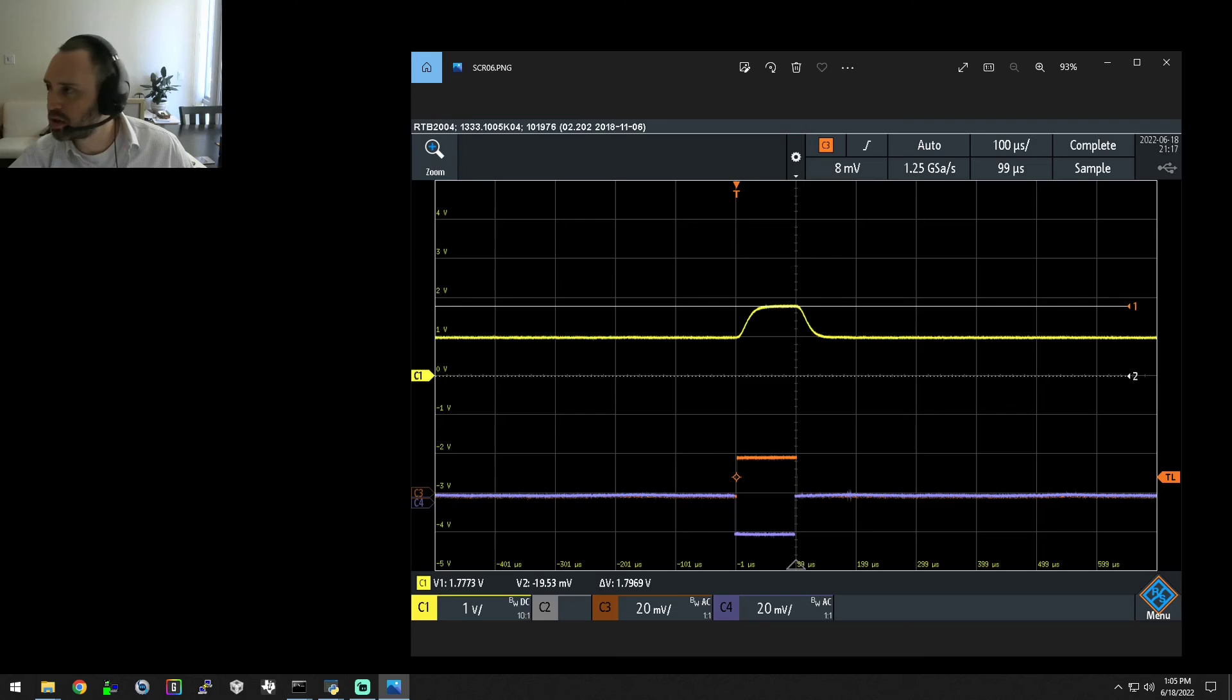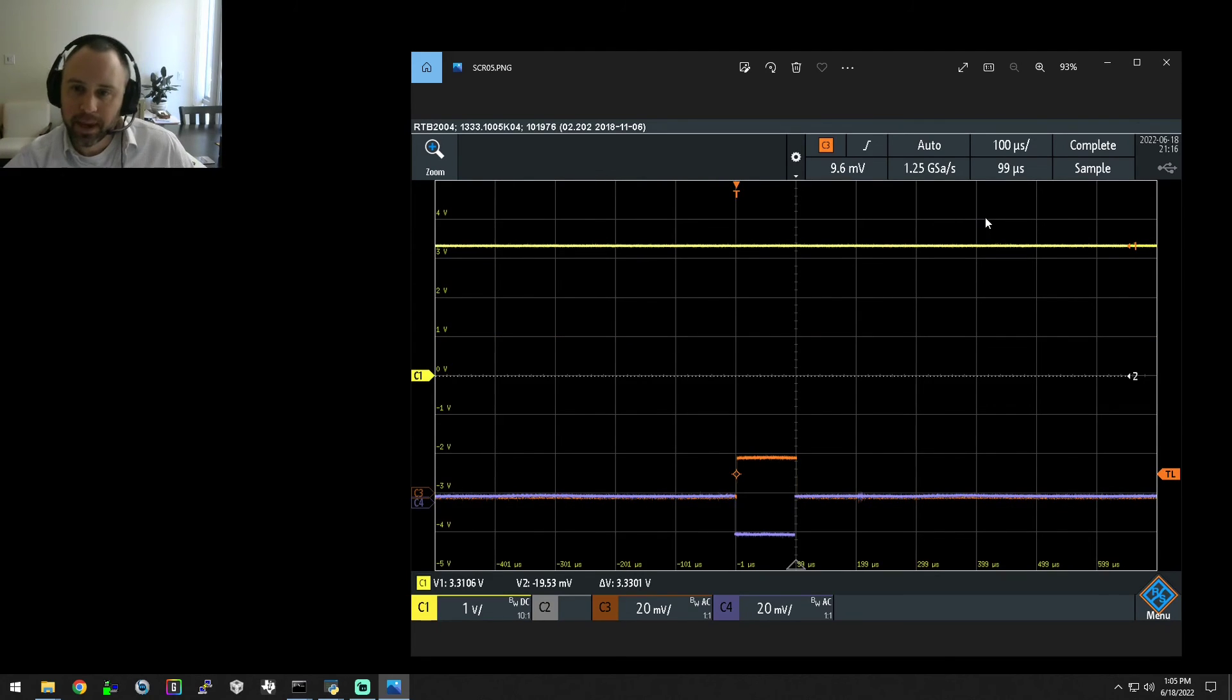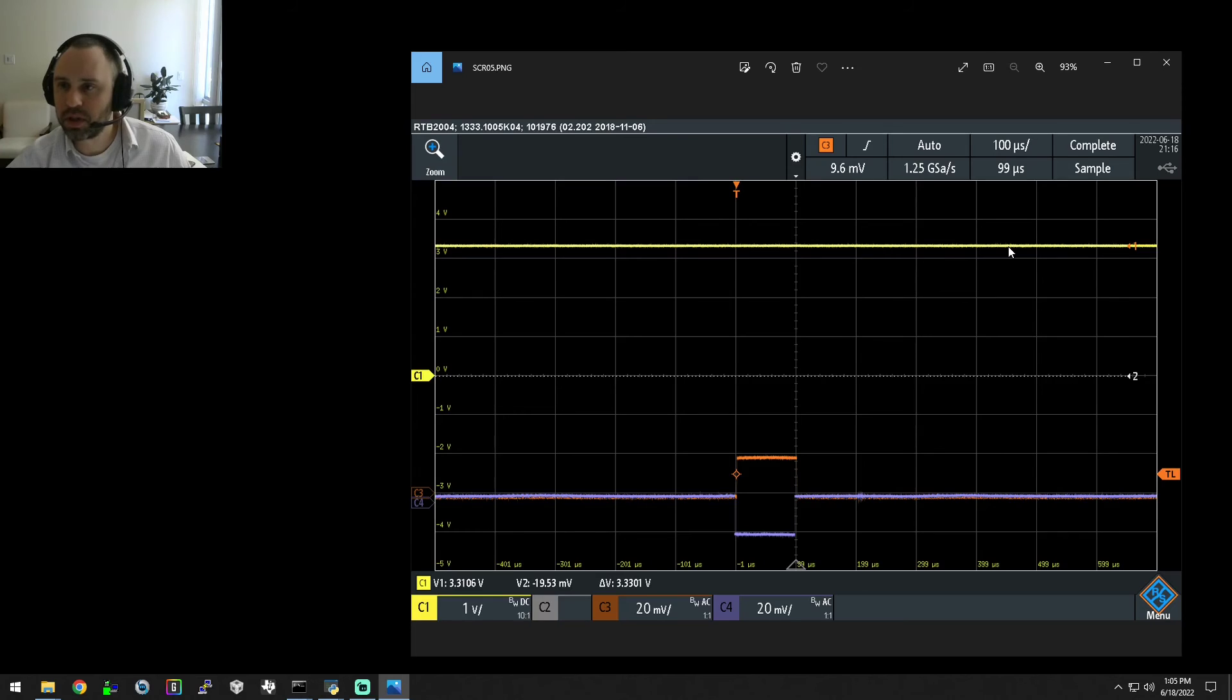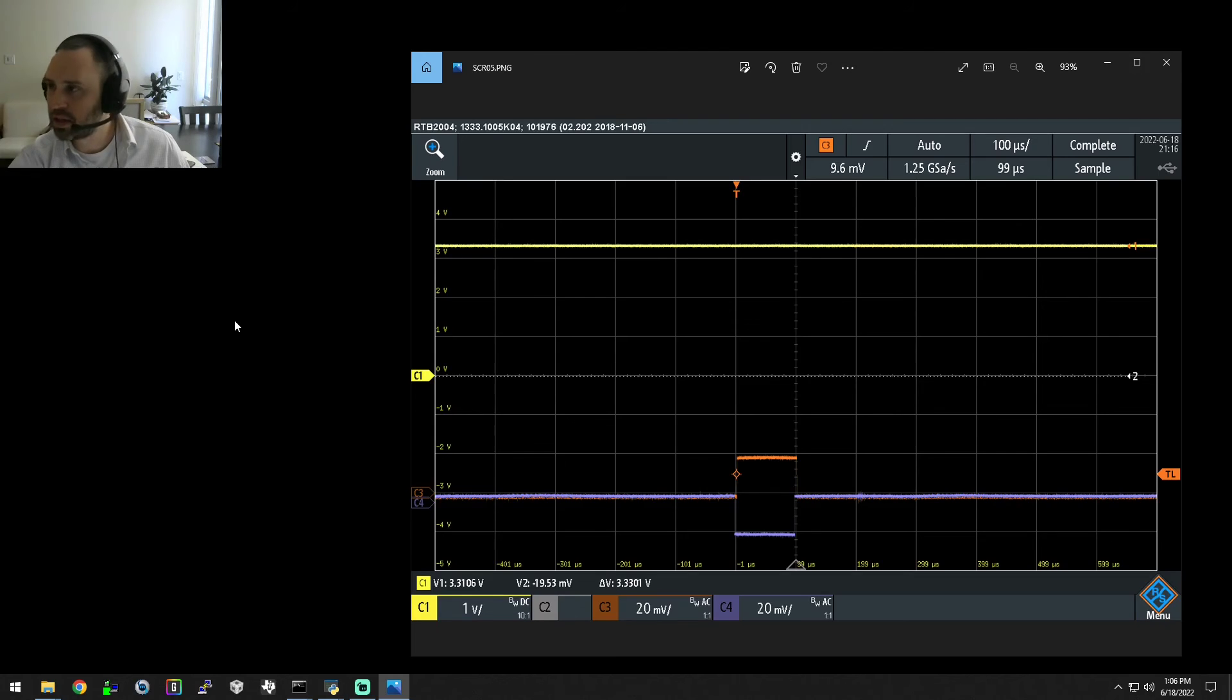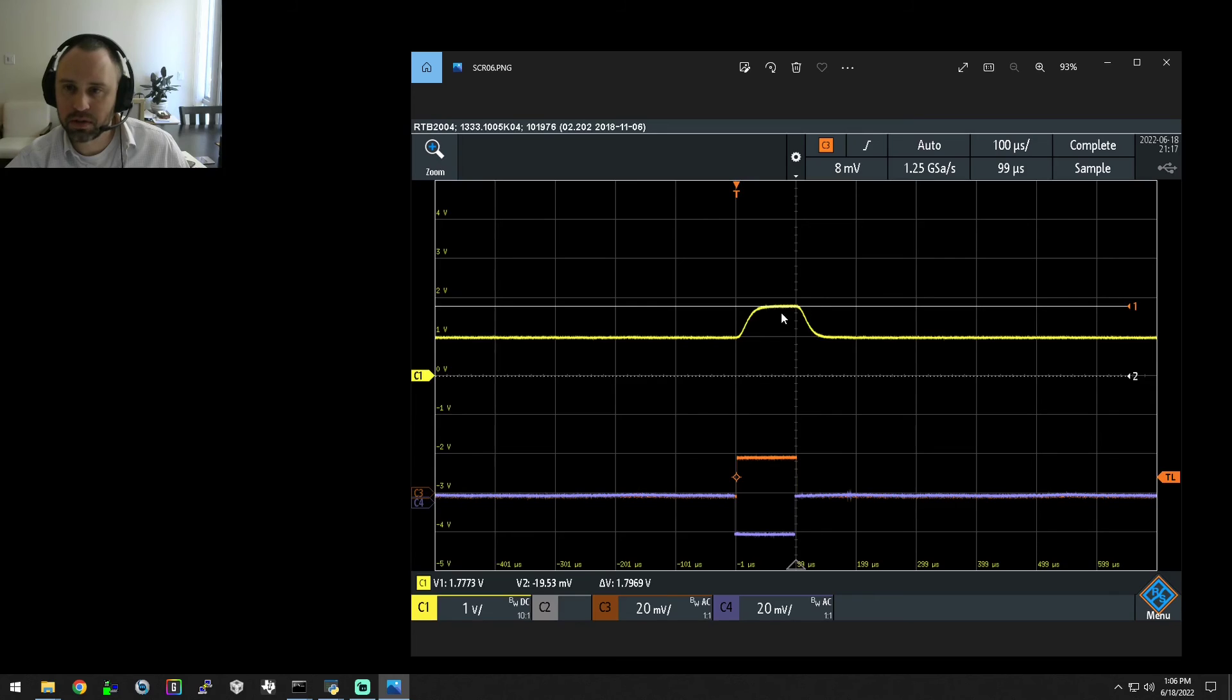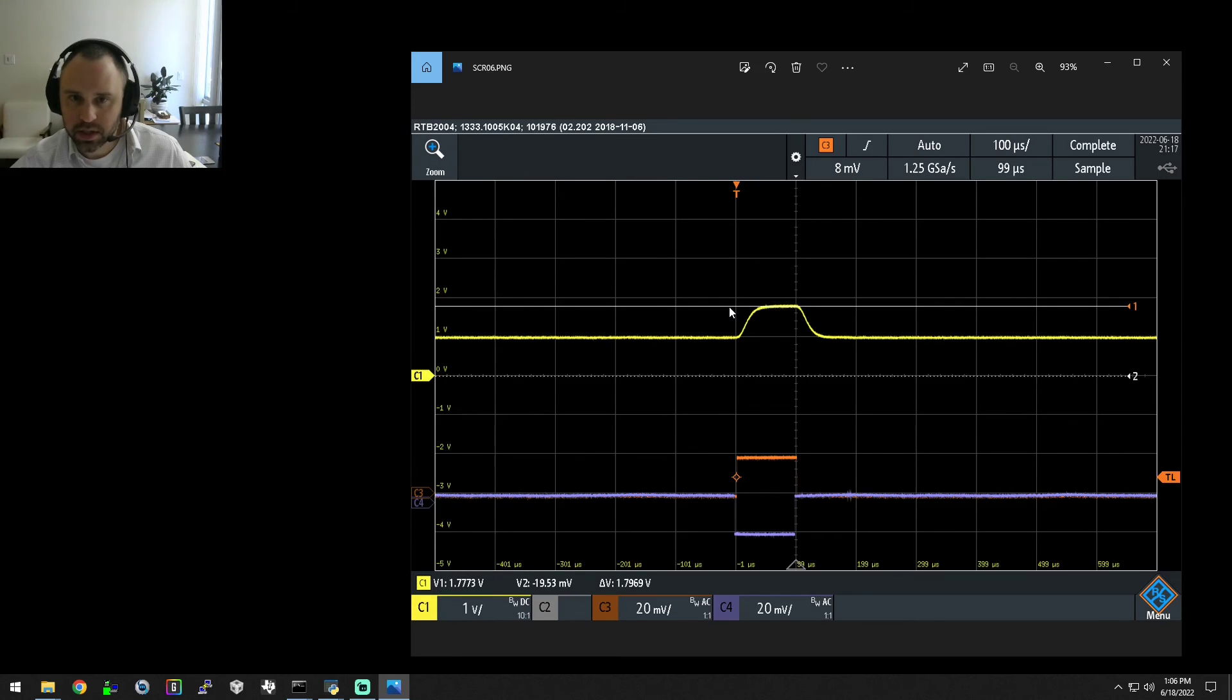This is just a result - this is a screen capture right at the A to D of a lab unit we modified to show the saturation here, which we saw in the data file. And then to fix that, once we walked the DC offset down to channel 1, you can see you get your DC offset down to 1 volt with your 800 millivolt pulse with a gain of 20, with your 800 millivolt pulse here.